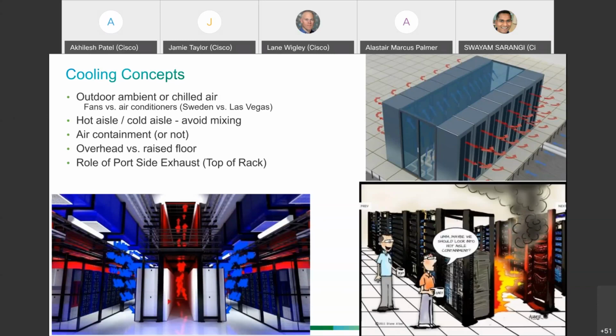The most efficient approach is really good air containment, either fully contained like the picture on the top right, or just relatively well contained. The picture on the bottom left is from that 800 megawatt center, where cold air comes in from the ceiling but the exhaust is contained and routed up to the top of the building and out into the desert, since they're not trying to recool that air, just getting rid of it. There are some cases in routers where this shows up too.